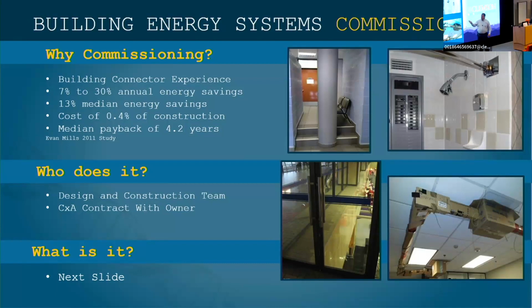A quick example: we did a high school auxiliary gym addition. They built this big auxiliary gym with a connector that tied into the existing building. Easy, right? Walk away, great. Well, during the winter, our minus 6.6 degree winters, I got a phone call. They said we cannot keep this connector above 30 degrees. I said that's not good, because we have fire sprinklers in there, and they're going to freeze and flood everything.